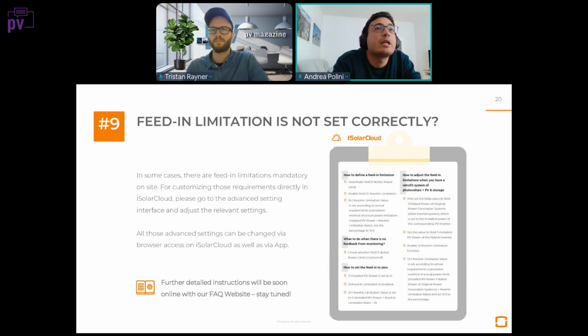And for the Sungrow inverter, the feed-in limitation settings are done either during the first commissioning, when you have the option to choose if you want to do feed-in limitation or not. In Germany, the standard until now is a 70% feed-in limitation, and thankfully this standard will be removed in January next year, so it will be allowed to feed in the whole power for small residential installations. But until now, you need to actually set up the feed-in limitation.